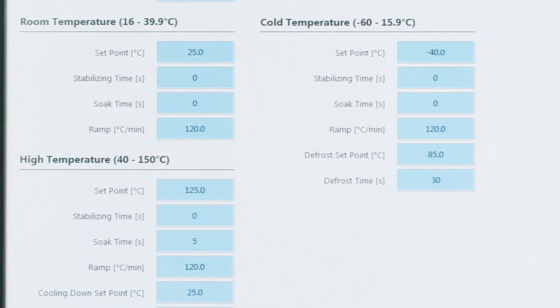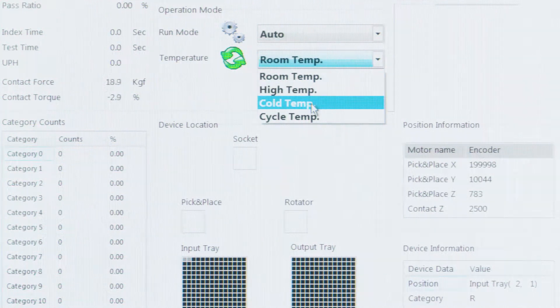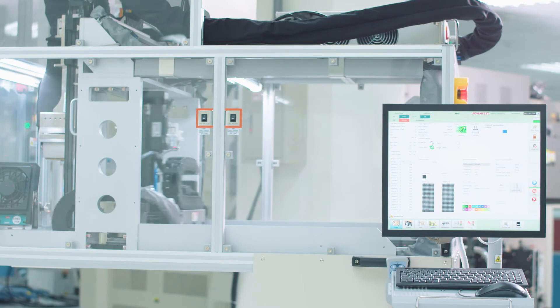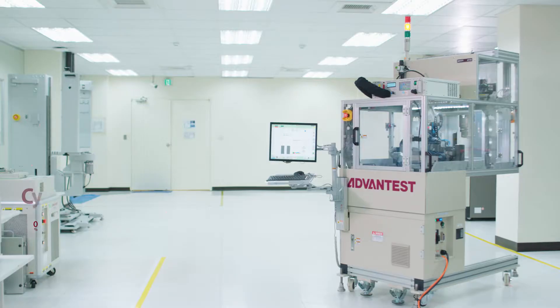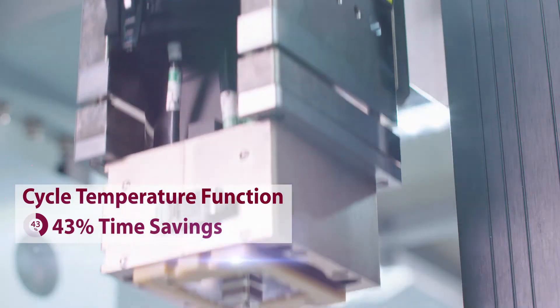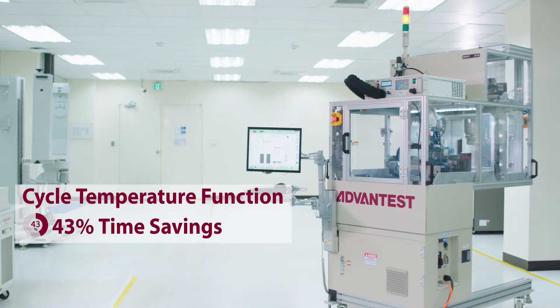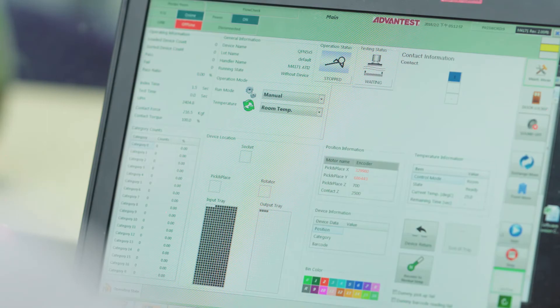In addition, the system's ability to quickly switch temperatures enables the M4171 to improve cycle times by more than 40% compared to manual thermal control solutions. Using the cycle temperature function with one insertion, a user can define the desired thermal ranges and cycle times for devices under test. A highly user-friendly GUI makes operation simple.